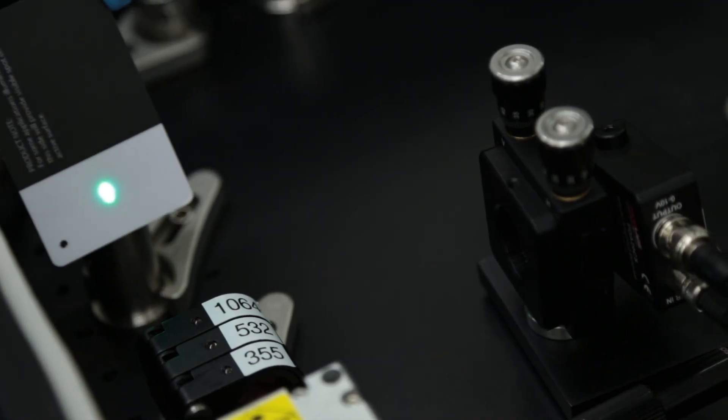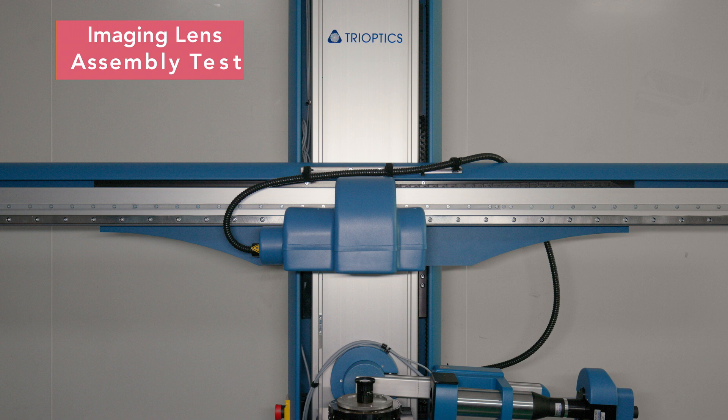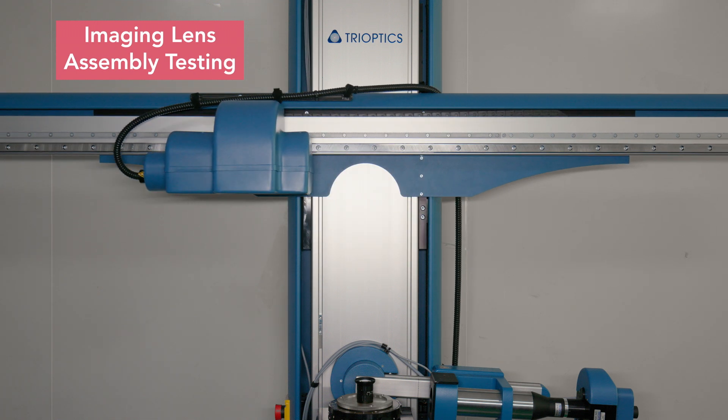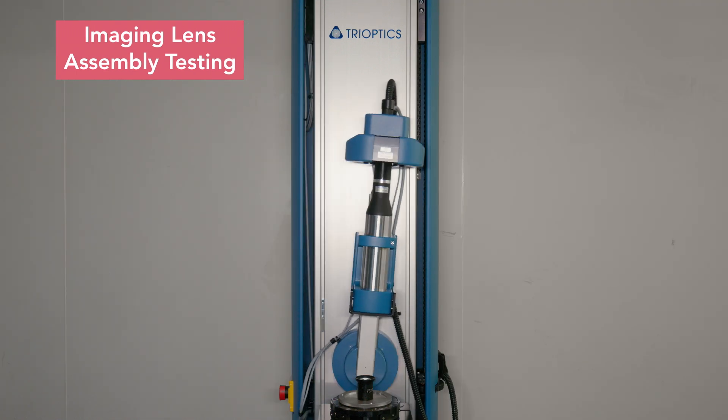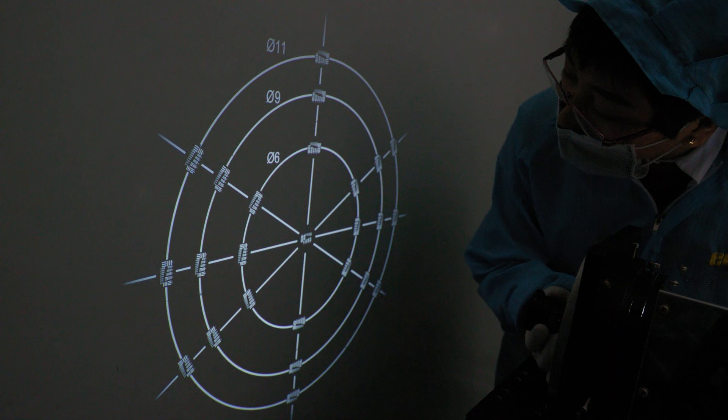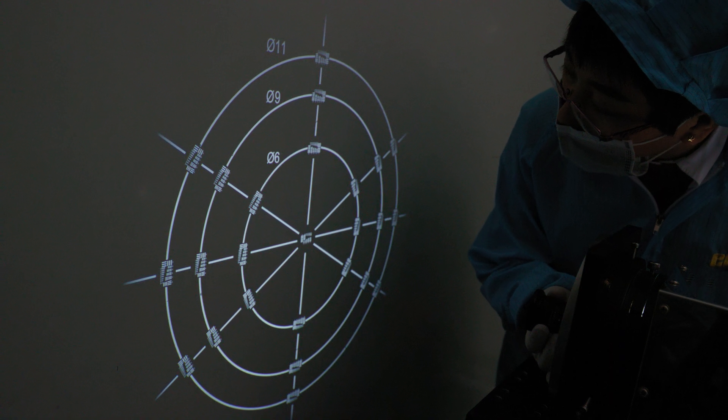The resolution and contrast of imaging lens assemblies are tested using MTF or modulation transfer function, test benches, reverse projection, and custom test fixtures.